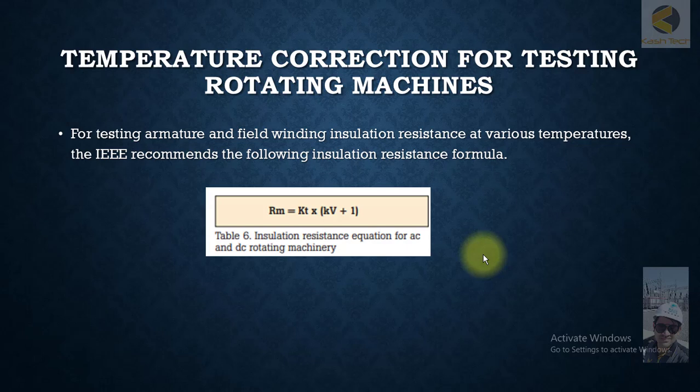For example, you are testing insulation at 40 degrees centigrade, next year you are doing it at 30 degrees centigrade, and third year at 20 degrees centigrade. All three are different, so you can't compare it. So the principle is that we are converting the resistance to an equivalent 20 degrees centigrade.